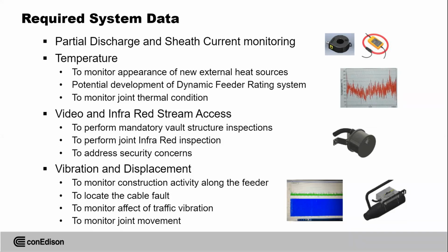So we can also perform joint infrared inspection. That infrared inspection will help us understand if there is any overheating going on with the joints. We know that over the life of service, cable joints experience different forces, and that may lead to movements, which may lead to some physical damage, small damage, but that small damage can start overheating locally, and an infrared camera can help to find it. And also the cameras can address security concerns. Basically, if somebody wants to enter the manhole without authorization, you will see live video footage of it.